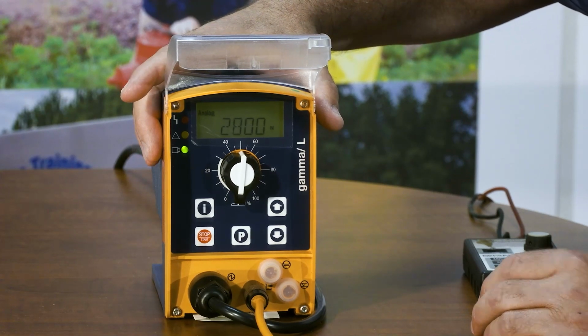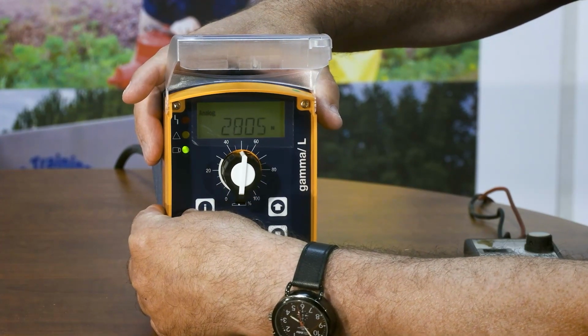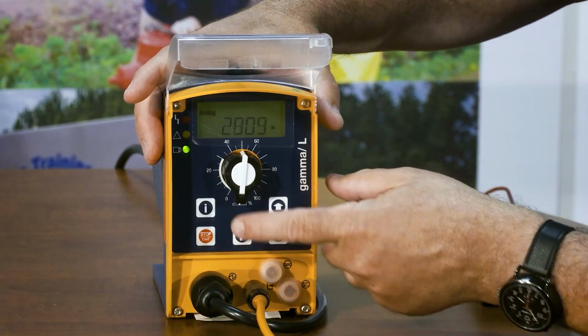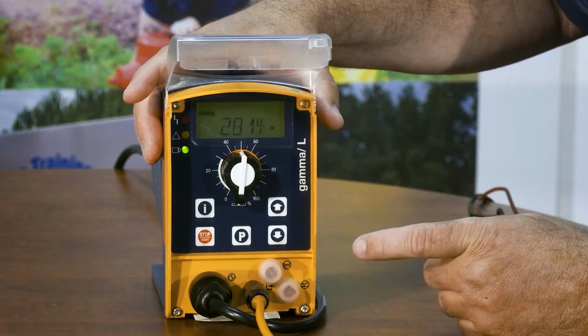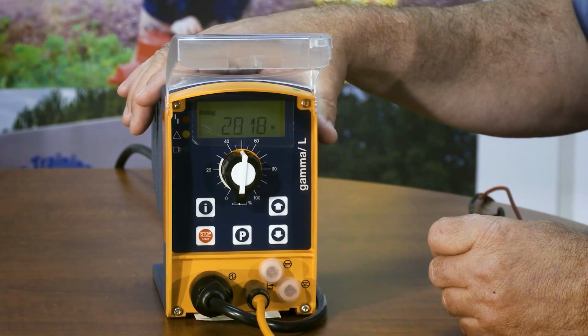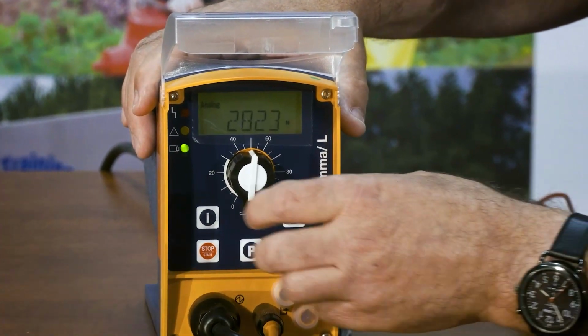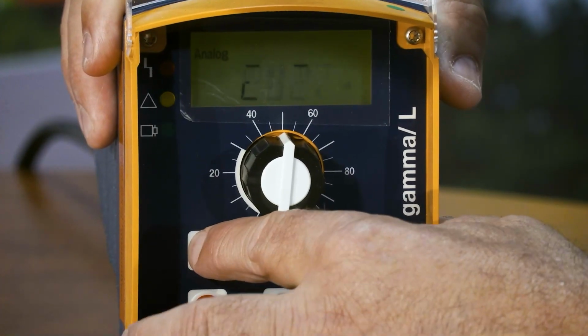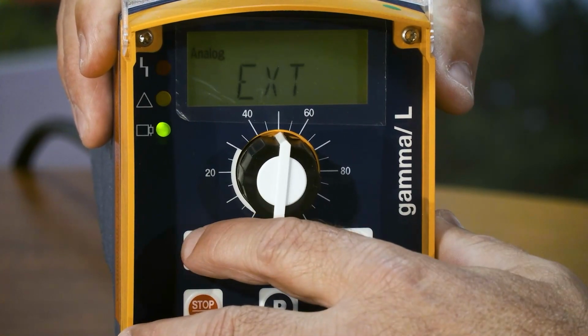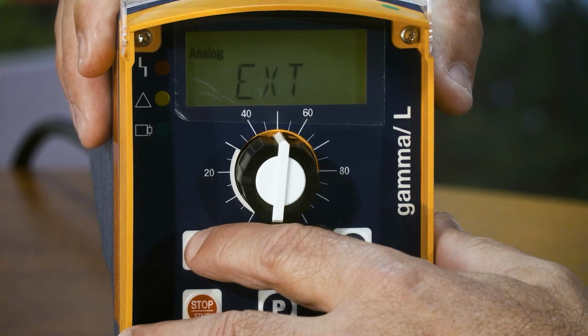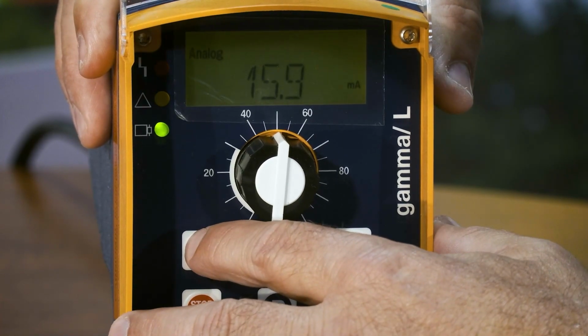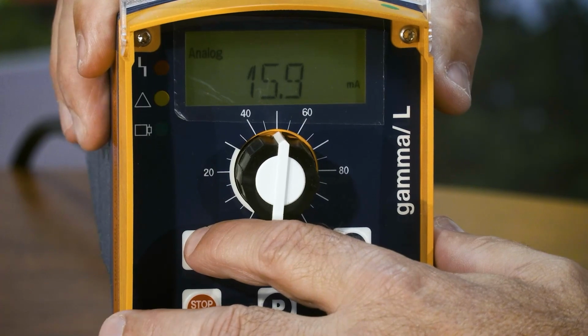Troubleshooting settings will vary by the type of chemical feed pump. The most basic example of this would be that a setting has been inadvertently adjusted or initially set incorrectly. This may require adjusting the pump settings through trial and error. When doing this, it is very important that you record what settings are changed and to what values. This is the only method to track how pump performance is affected by pump settings.